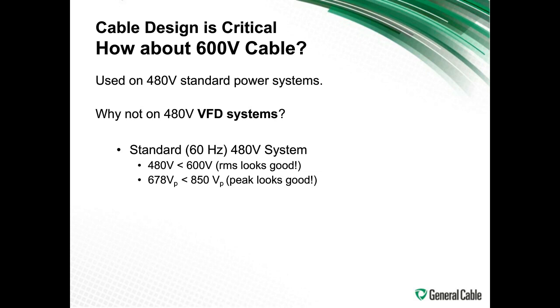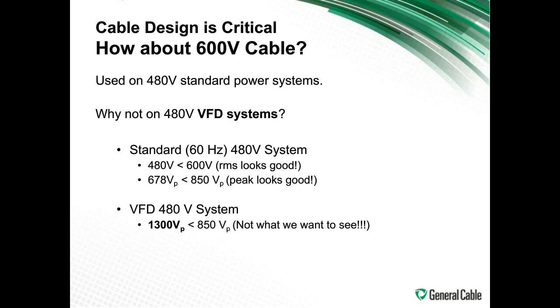If you look at a 480 volt system for VFD drives, you're going to get 1300 peak voltage. That is not going to work when you actually have a 600 volt cable, because it's rated for 850 volt peak. Also, the high frequency pulse width modulation is going to add that stress that we were talking about with the high dV/dTs.